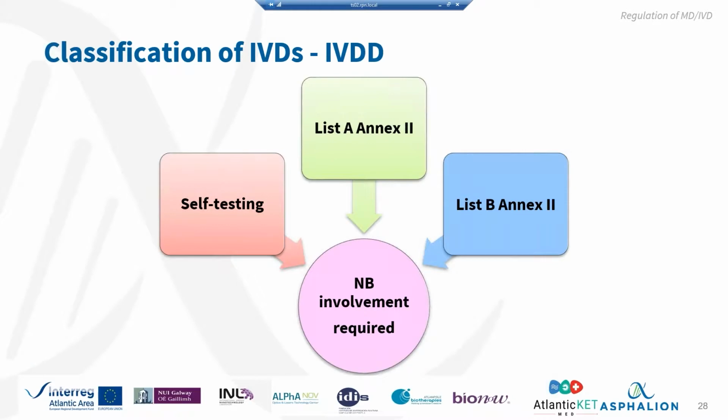So which devices required notified body involvement? Well, those that were either in list A, list B, or if they were for self-testing. Devices that were supposed to be used by the patient were also assessed by notified bodies. Okay.